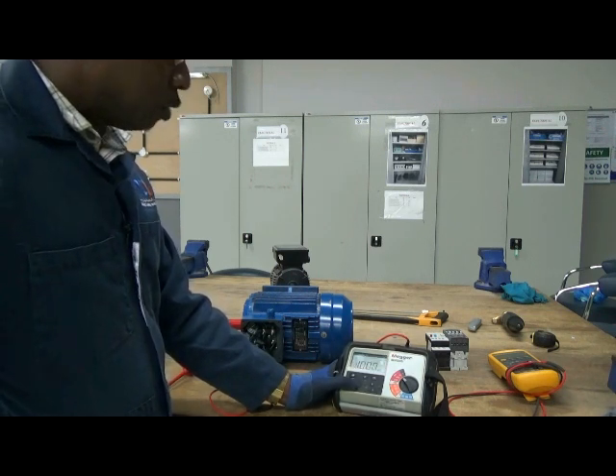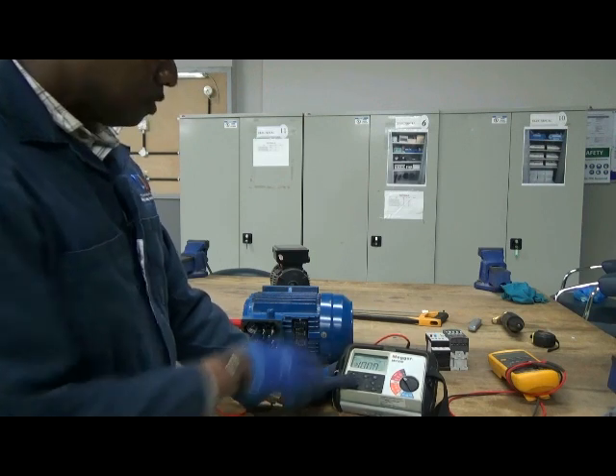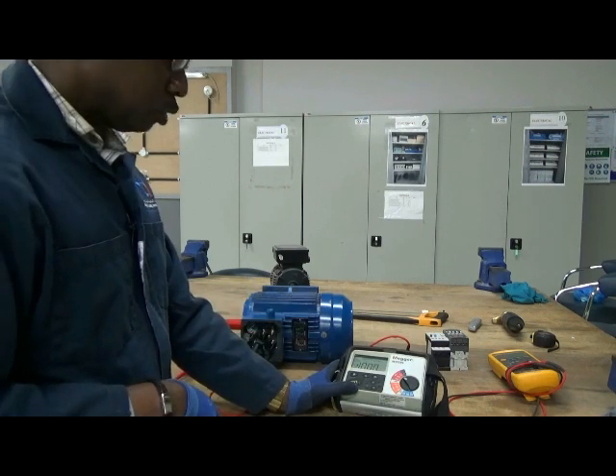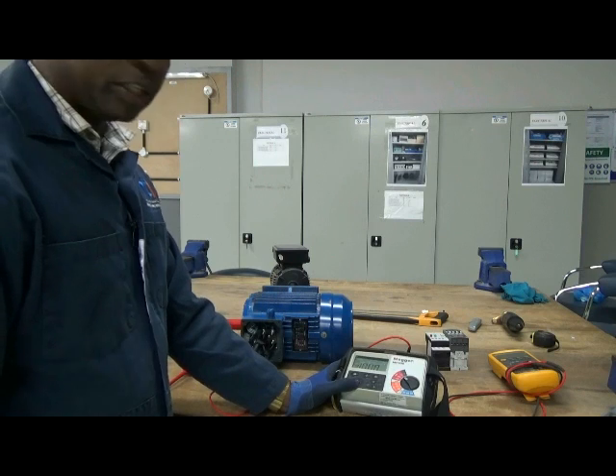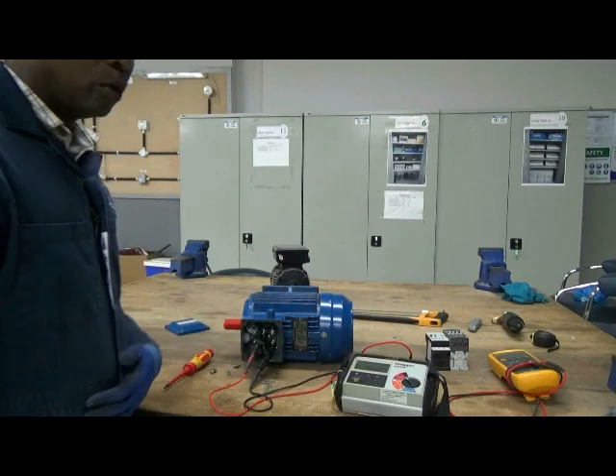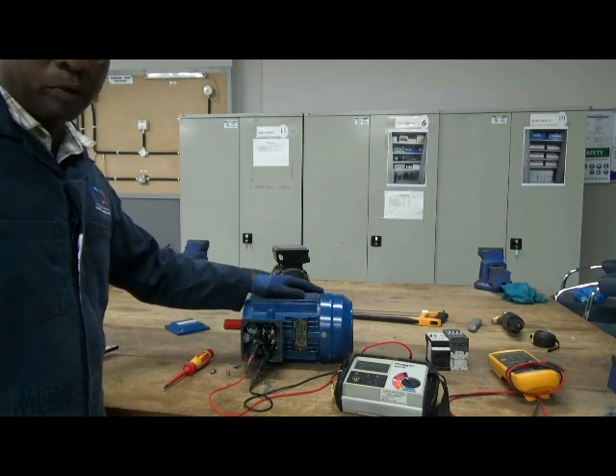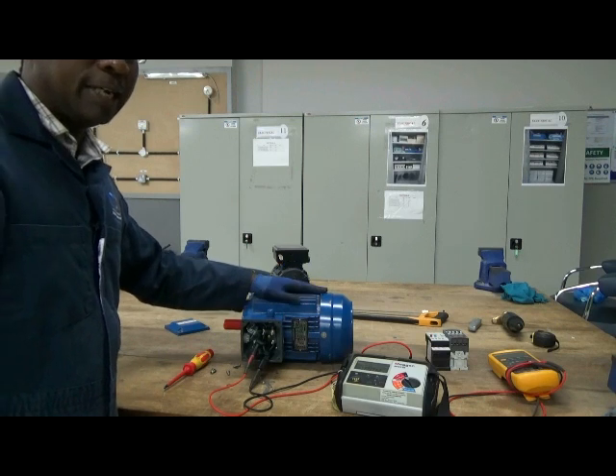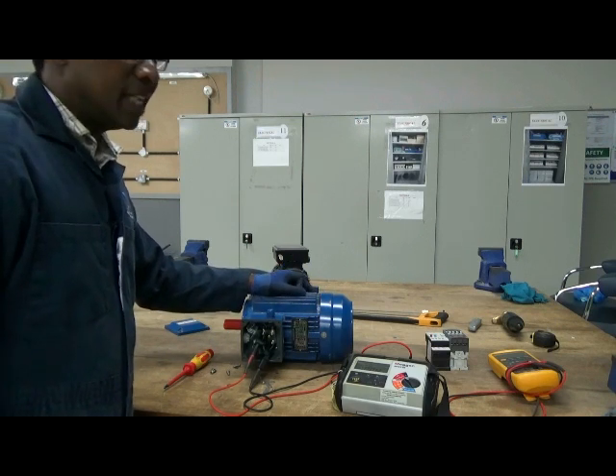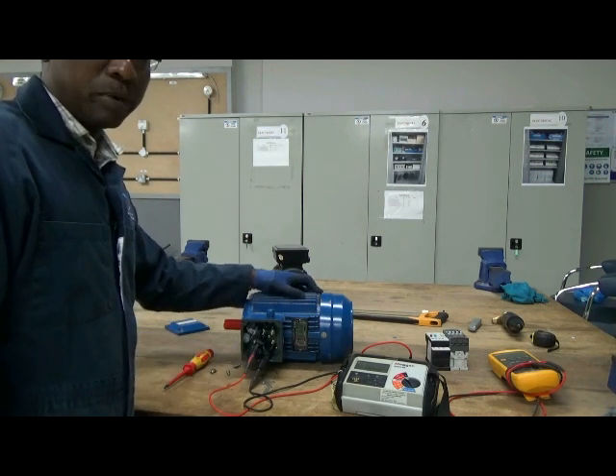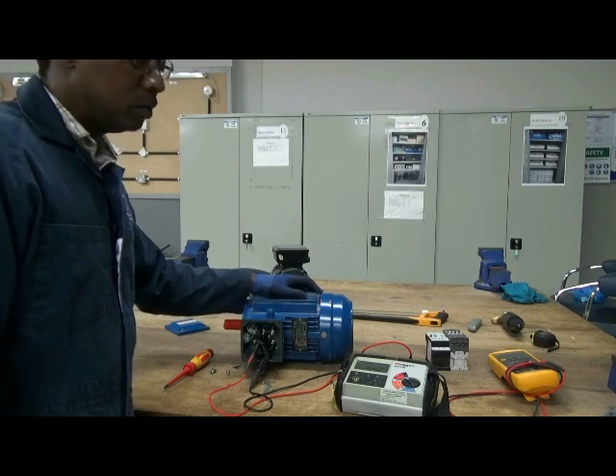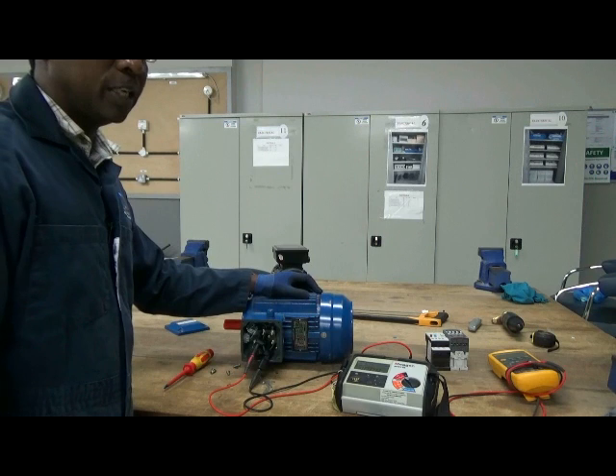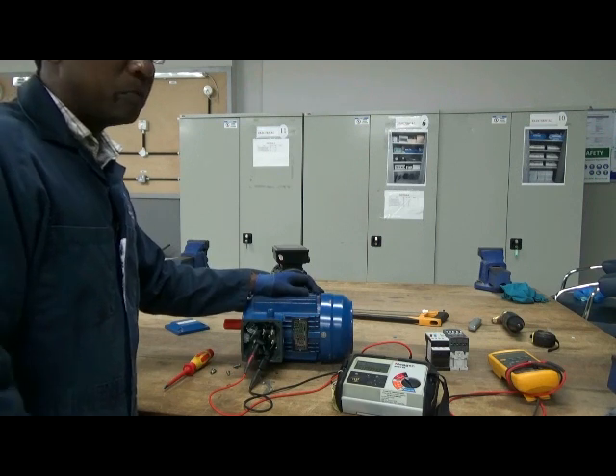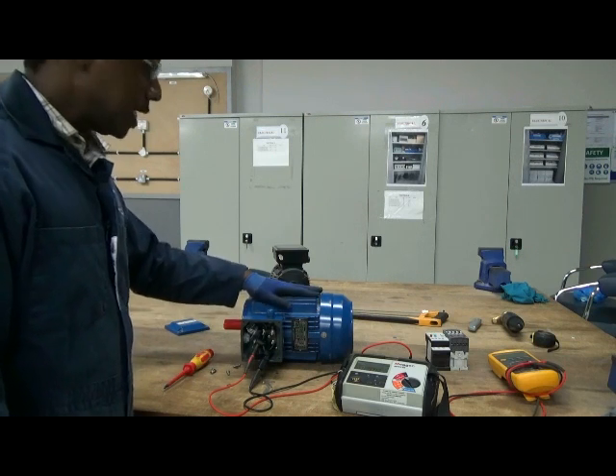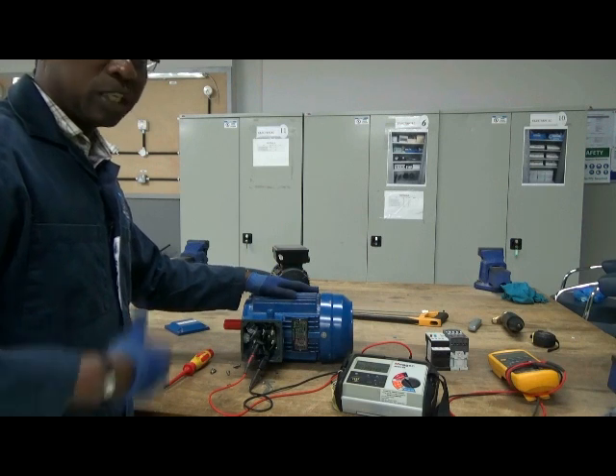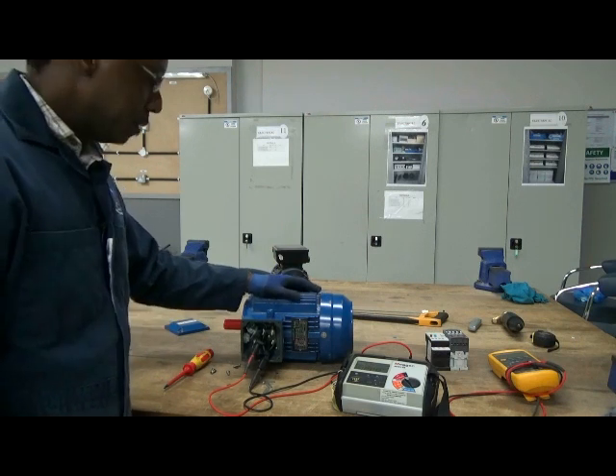All engineers all over the world talk the same language. So even if you go and peruse your own regulations or rules, they will tell you the same thing, that the insulation resistance of equipment should not fall below 1 mega ohm. This is treated as fixed equipment. Portable equipment and domestic electrical installations would only require something like 0.5 mega ohms. That is acceptable in a house, a commercial building or portable equipment. But fixed equipment like electric motors, transformers, and so on require not less than 1 mega ohm.